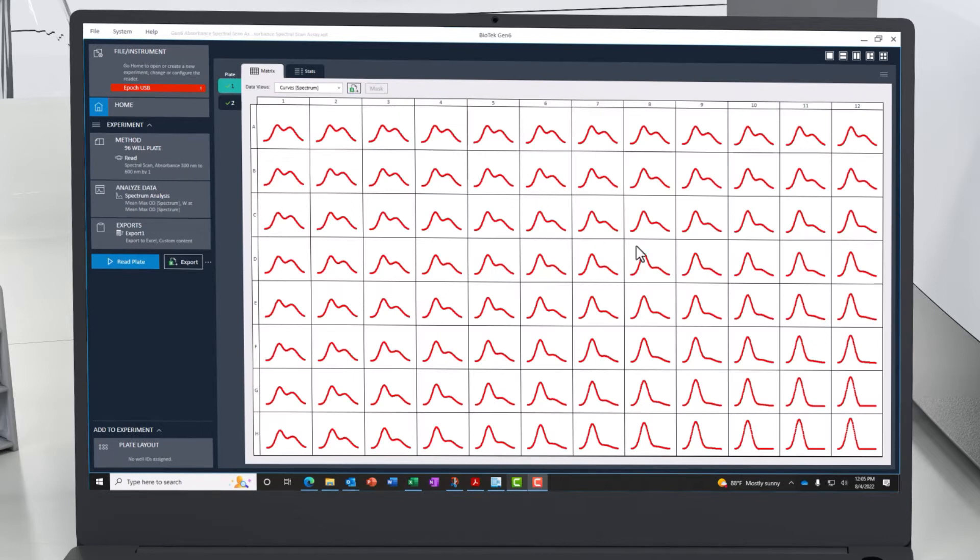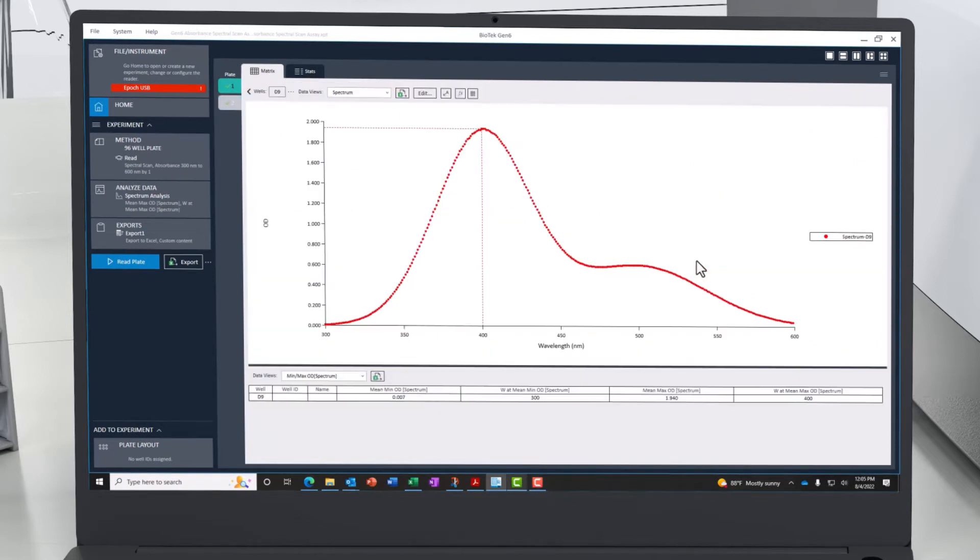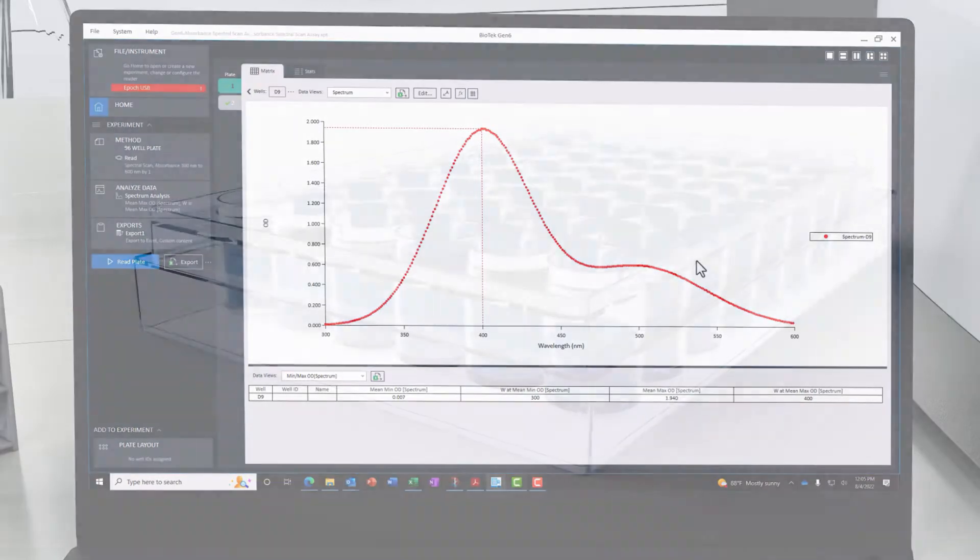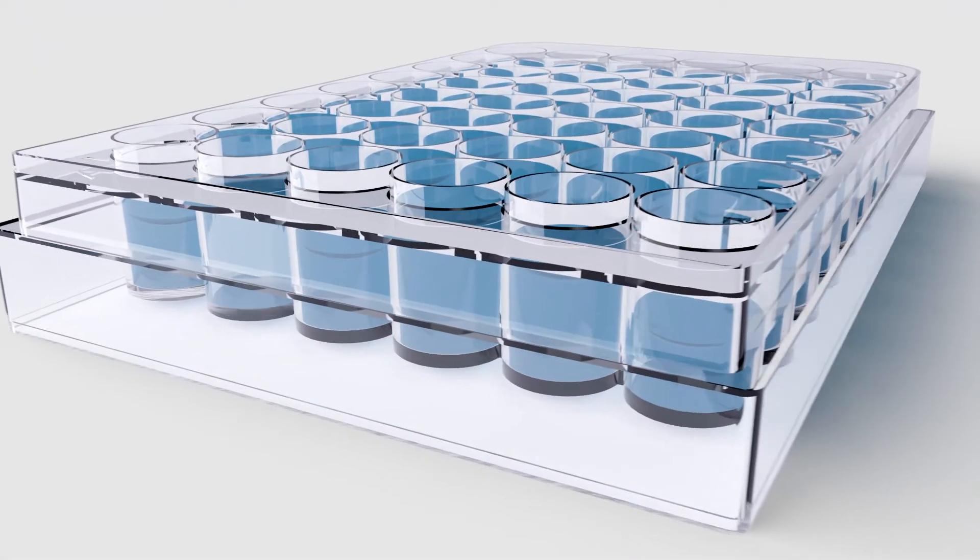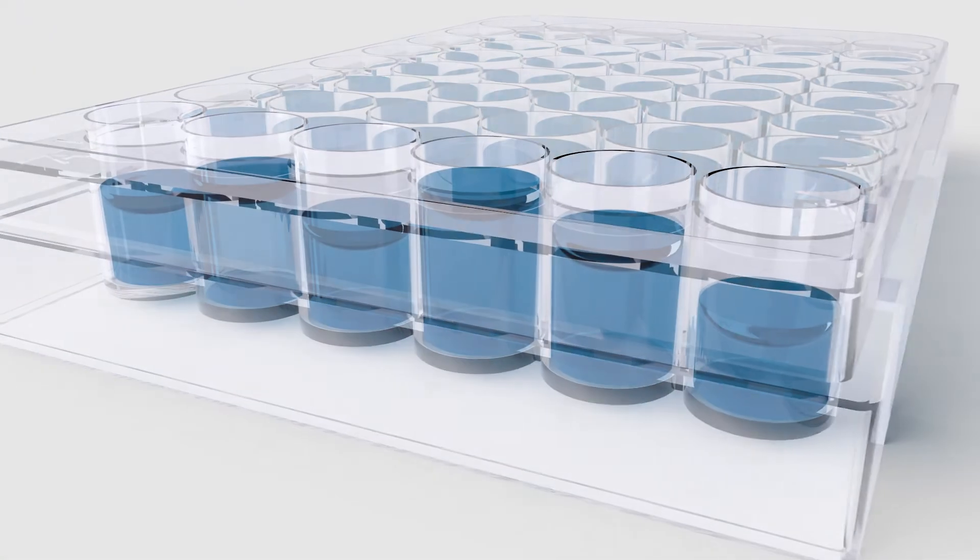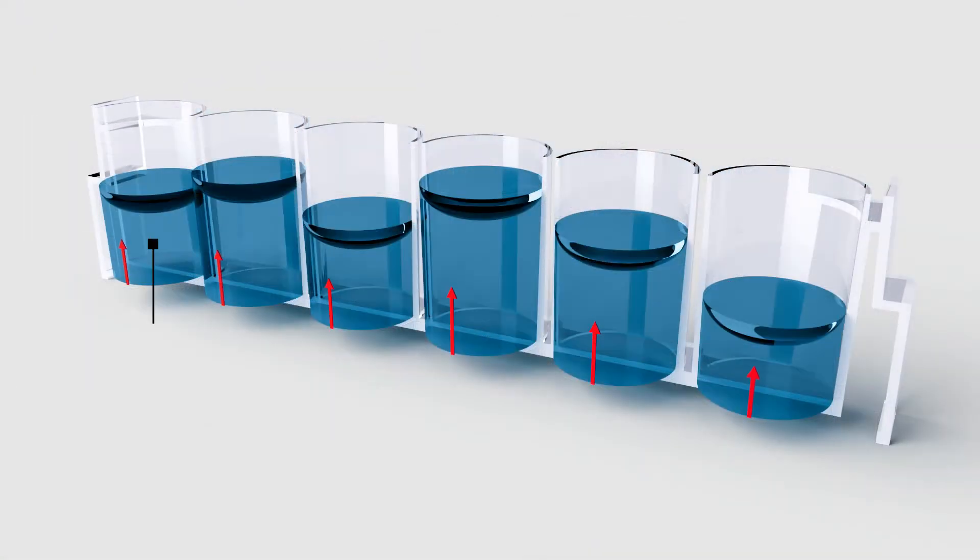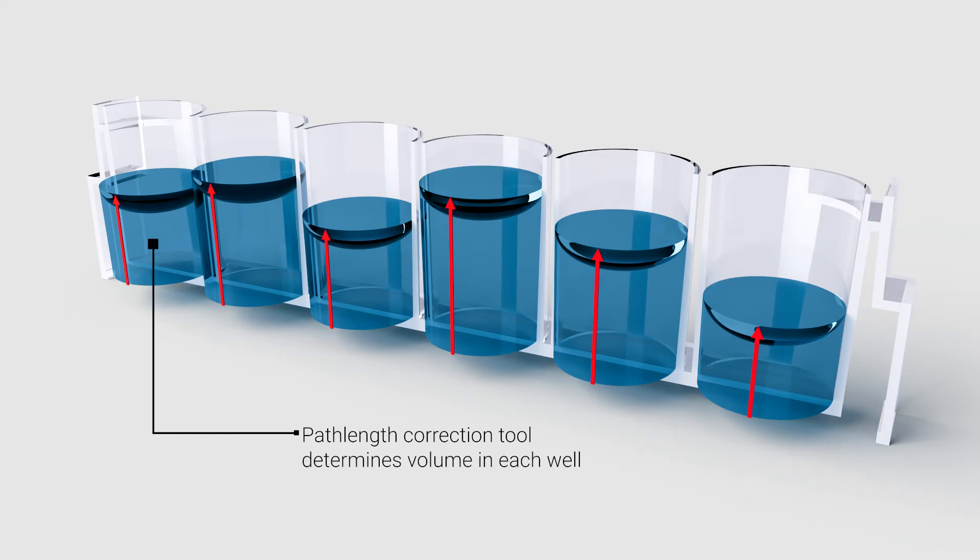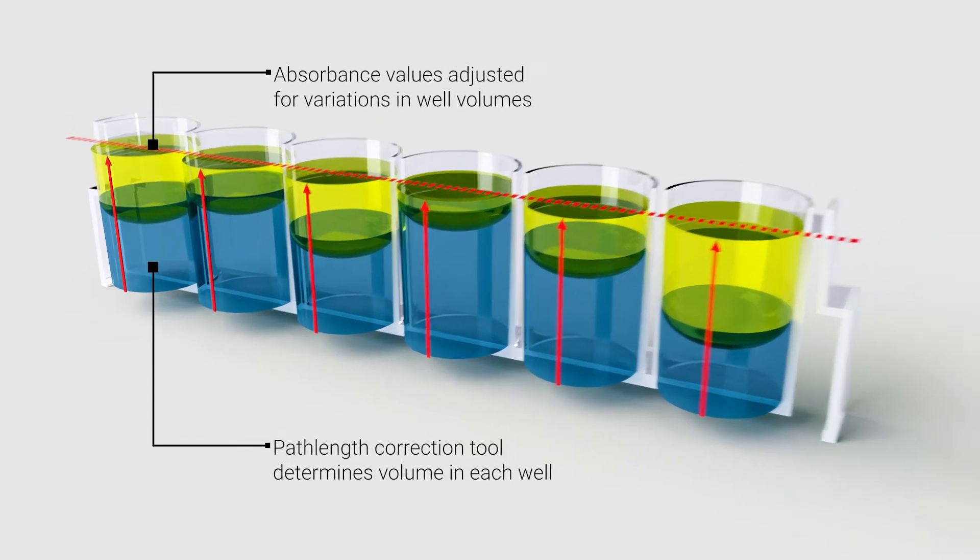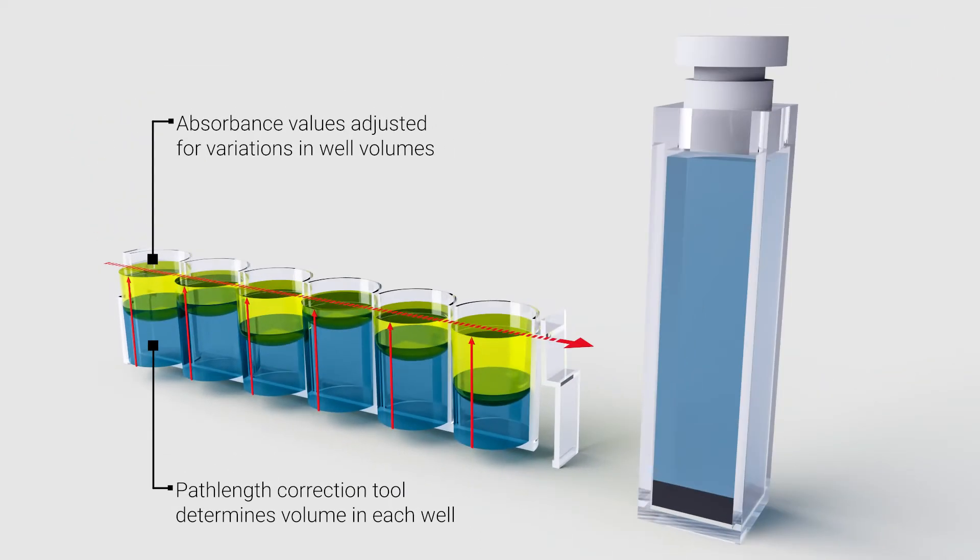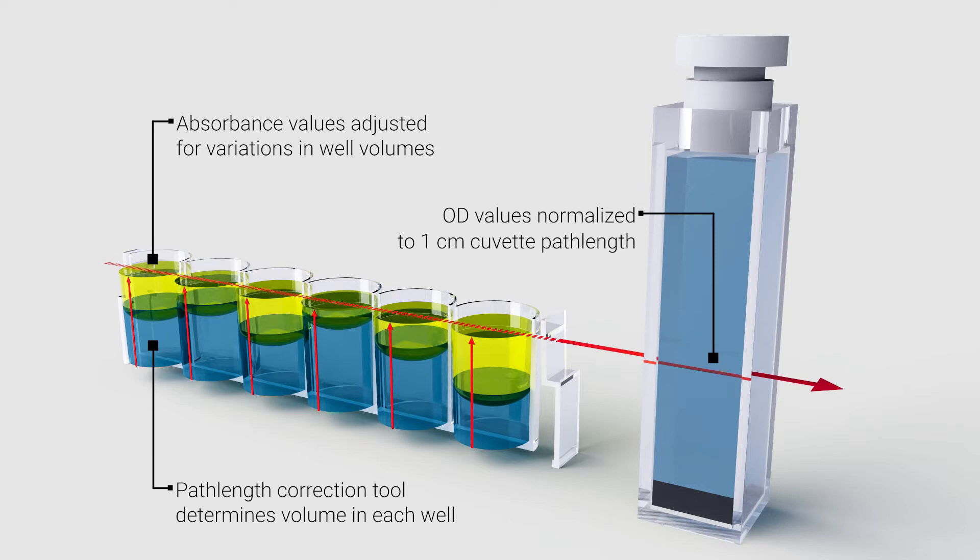Spectral scans of unknown samples can automatically determine the optimal wavelength to use for future experiments. To adjust for potential pipetting variations from sample to sample, an automated path length correction tool can be incorporated to ensure accurate values are returned. OD values are normalized to a 1 cm equivalent path length as if the system was reading in a cuvette.